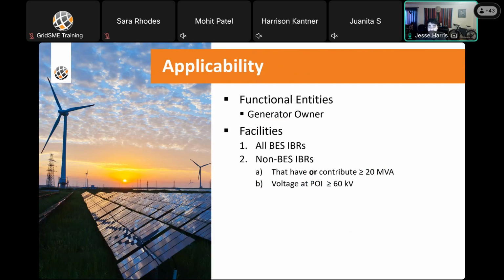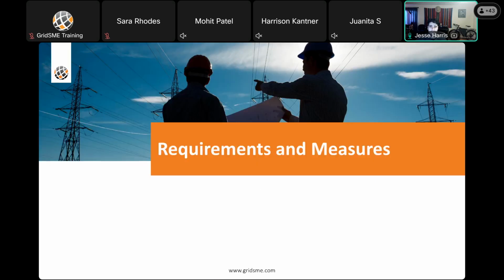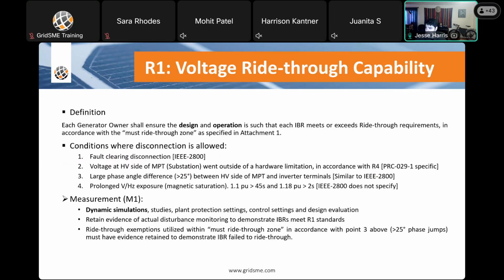So the applicability, pretty straightforward. Any generator owner, all BES IBRs, and if it's a non-BES IBR, if you have or contribute more than 20 MVA, and your voltage at the POI is greater than 60 kilovolts, PRC-29-1 applies to you. All right, so what criteria need to be met, and how can we prove that we are meeting those criteria? So there are 4 requirements, and I'll go through those in detail right now.